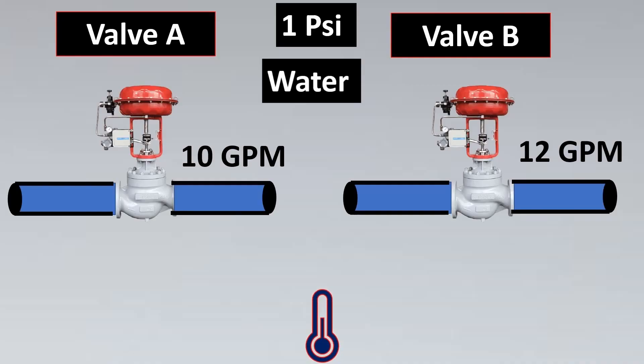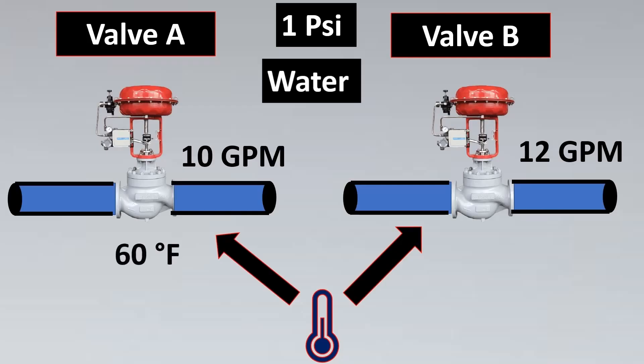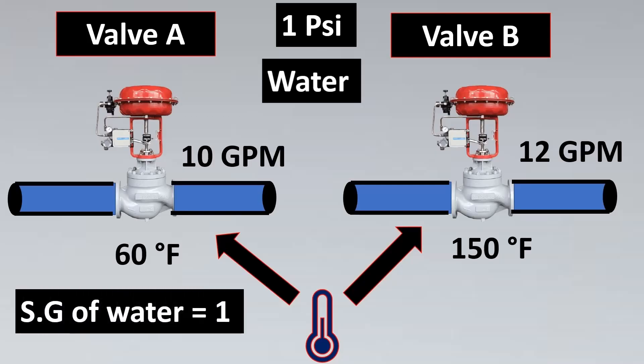That parameter is temperature. Both valves using water might have different temperatures — one maybe at 60°F and the other at 150°F. As temperature increases there is again a difference in flow rate, so we have to maintain a constant temperature as well. We will select 60°F. A lot of people ask why 60°F is specifically taken in the CV definition — the answer is because the specific gravity of water is 1 at 60°F, which helps greatly when doing CV calculations.